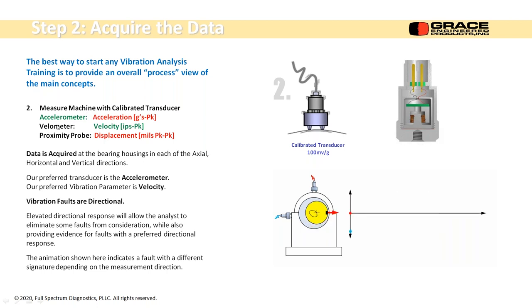So what we do instead of measuring velocity directly, we measure it with the accelerometer and we mathematically integrate it into velocity. Probably a little too much noise for most of the people out there. You don't really care about that, but that's the process. So that's why I have my green bolded accelerometer and the velocity parameter. And we'll talk more about that. Proximity probes are one of the other transducers. I believe that there's a way to pull those into the database as well if they're already installed on the machine. So data is acquired.